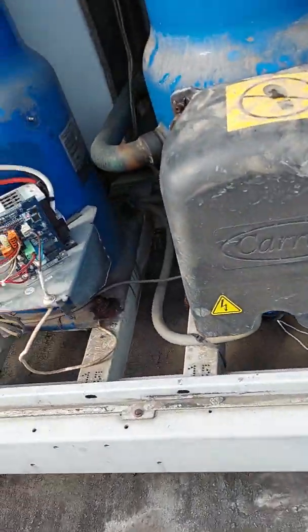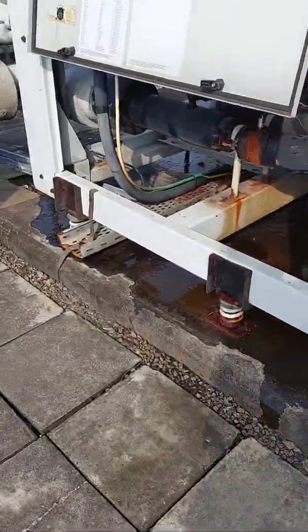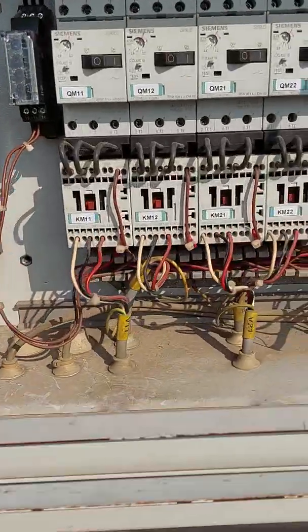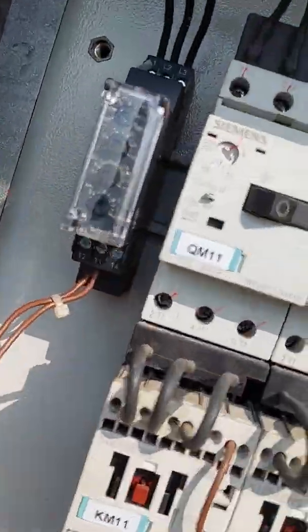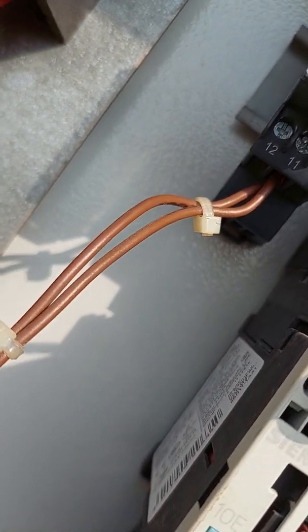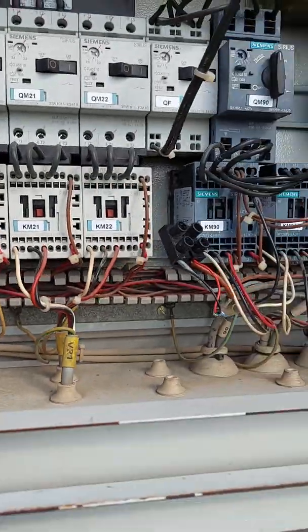Put this grease and cover this one back. Okay, this is the only one causing P28. We tried to troubleshoot — this is the one causing the problem. See, we now jump here to the bottom temporarily. We run this one temporarily, but we will update it. And once we have the spare phase monitor, we will run it.